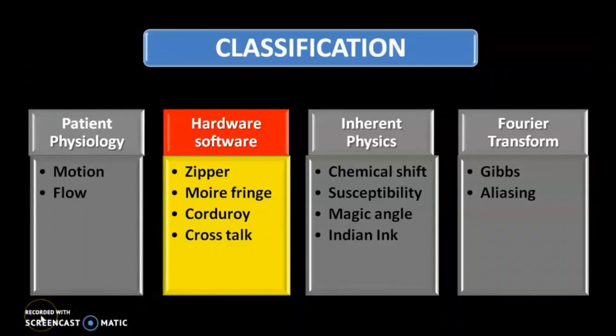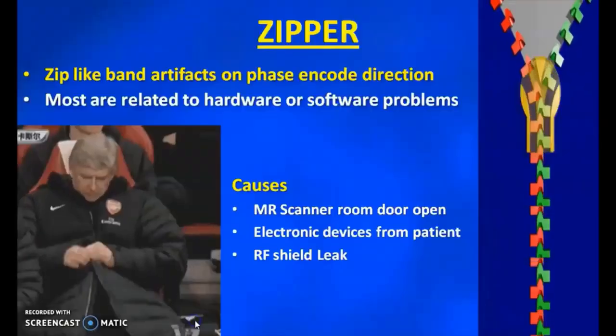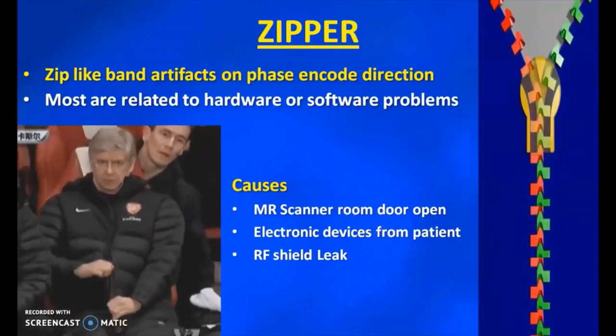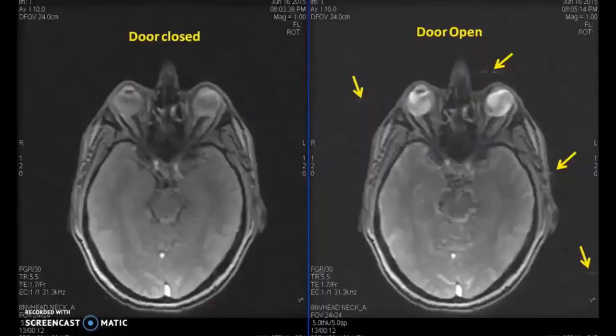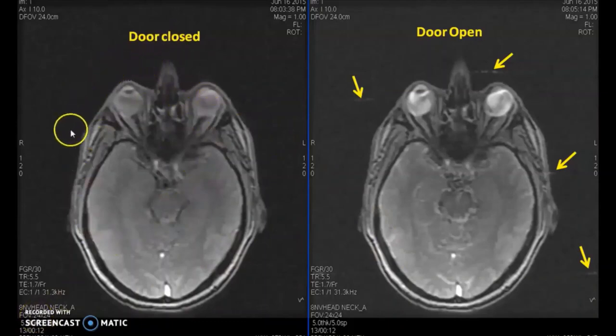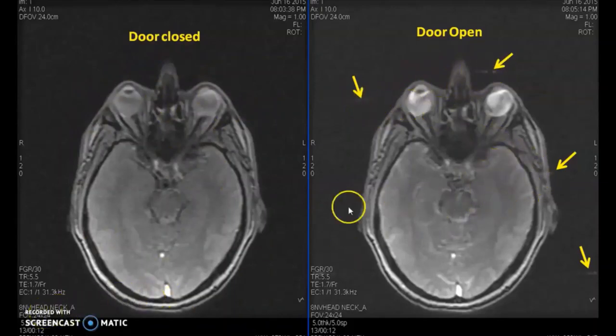Another classification is hardware or zipper-related artifacts. The zipper artifact is caused by an open MRI scan room door, or some faulty electrical devices from the patient or inside the room. Fused bulbs inside the room can also cause a zipper type of artifact. As an example, I did the three-plane localizer with the door closed — no artifact was seen. Then I kept the door open and repeated the same sequence, and the zipper-like artifact was seen.